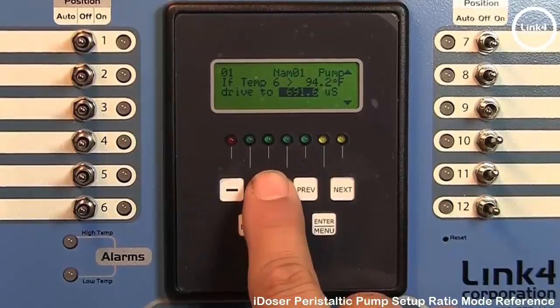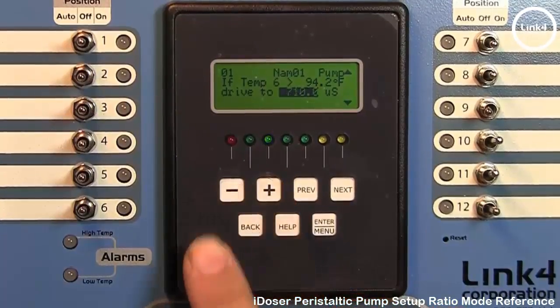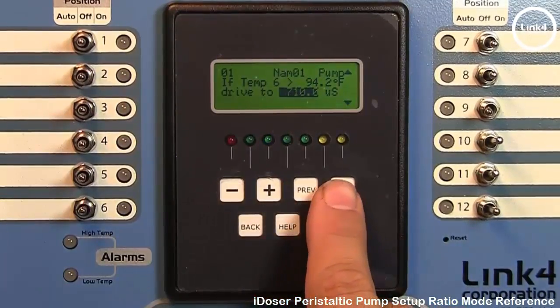And that's what you would do here. We'll put 700, 710, hit next. So if temp 6 is greater than 94.2, drive the EC to 710 microsiemens.